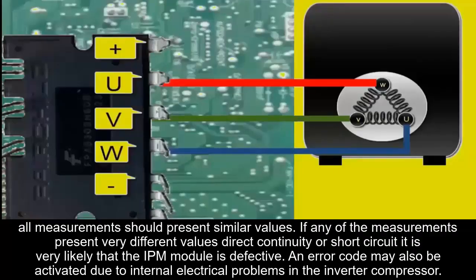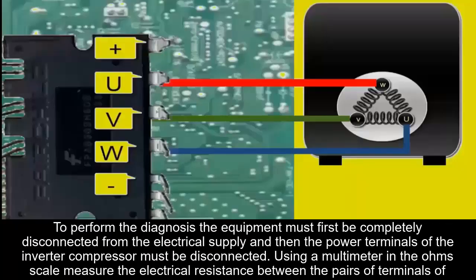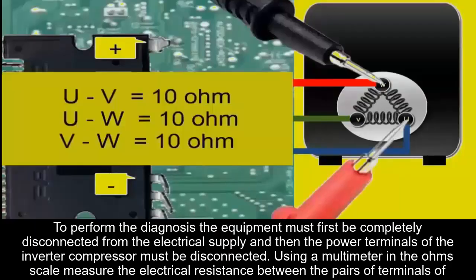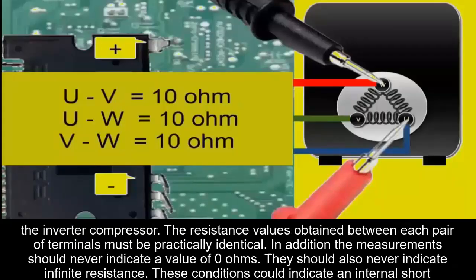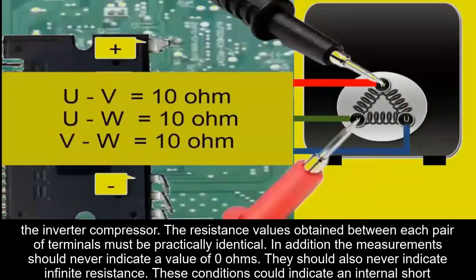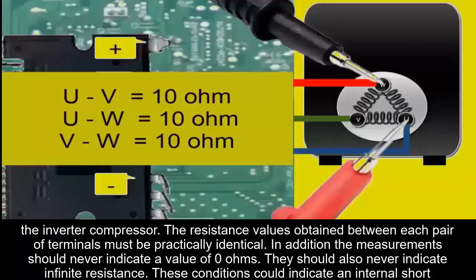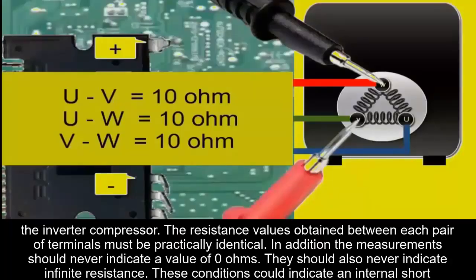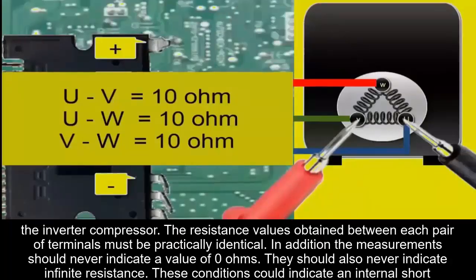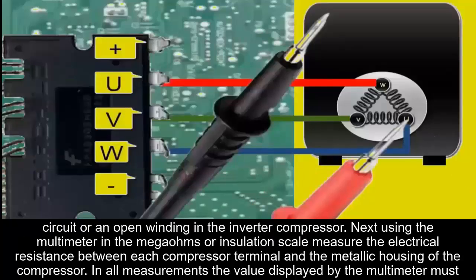An error code may also be activated due to internal electrical problems in the inverter compressor. To perform the diagnosis, the equipment must first be completely disconnected from the electrical supply, and then the power terminals of the inverter compressor must be disconnected. Using a multimeter in the ohms scale, measure the electrical resistance between the pairs of terminals of the inverter compressor. The resistance values obtained between each pair of terminals must be practically identical. In addition, the measurements should never indicate a value of 0 ohms. They should also never indicate infinite resistance. These conditions could indicate an internal short circuit or an open winding in the inverter compressor.